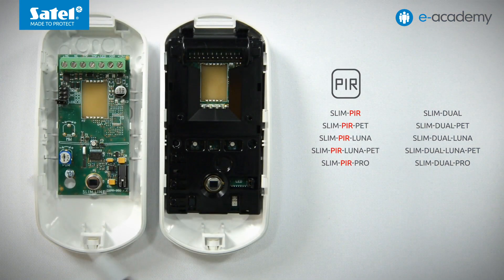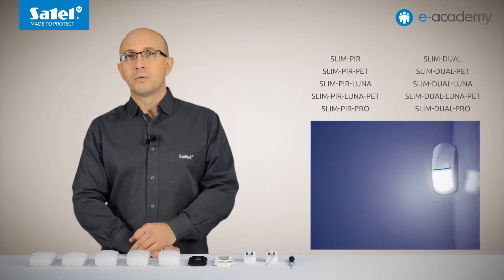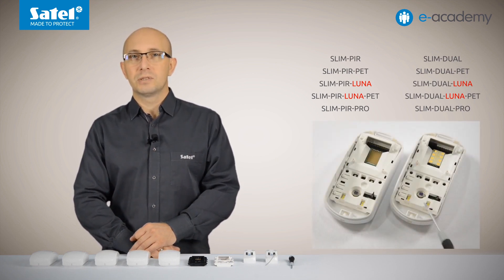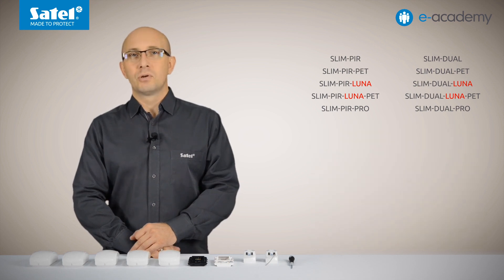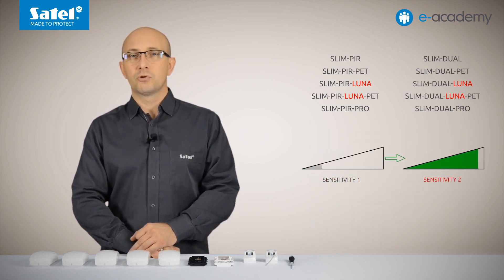The first five of them come equipped with a passive infrared sensor. The next five are dual-tech models, which in addition to the PIR sensor also have a built-in microwave sensor. The detectors with the LUNA designation in their name have a set of LEDs for implementation of the lighting feature. They also offer the option of programming two sensitivity thresholds and remote switching between them.